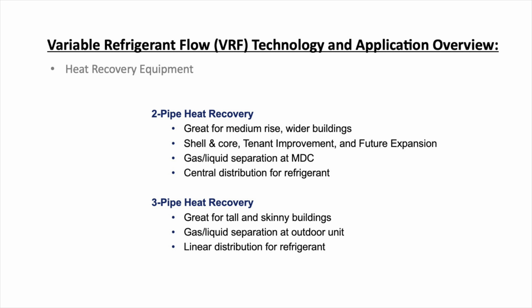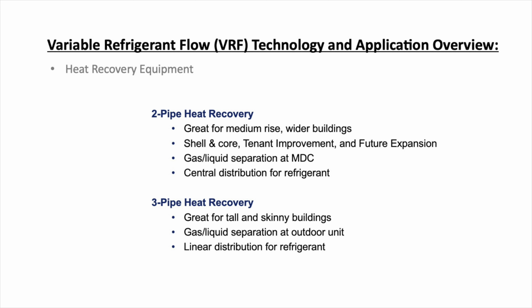A question that we get all the time is, where do we want to use 2-pipe versus 3-pipe heat recovery? You typically want to use 2-pipe heat recovery in a 1 to 2-story building. Wider buildings where you have a central location to mount your MDC. These MDC boxes tend to be larger, so placing them centrally in a building makes the most sense. And then you can home run to each indoor unit from that MDC box.